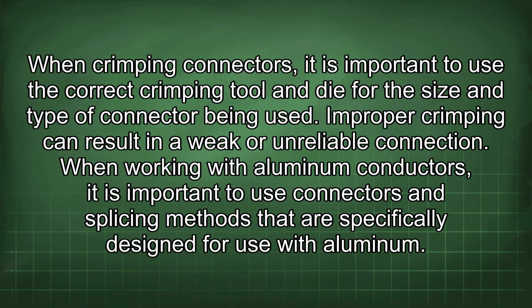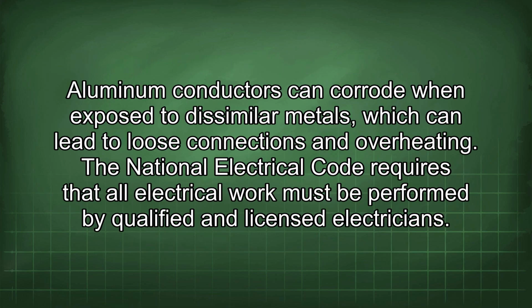When crimping connectors, it is important to use the correct crimping tool and die for the size and type of connector being used. Improper crimping can result in a weak or unreliable connection. When working with aluminum conductors, it is important to use connectors and splicing methods that are specifically designed for use with aluminum. Aluminum conductors can corrode when exposed to dissimilar metals, which can lead to loose connections and overheating.